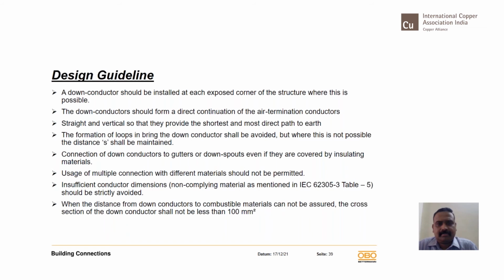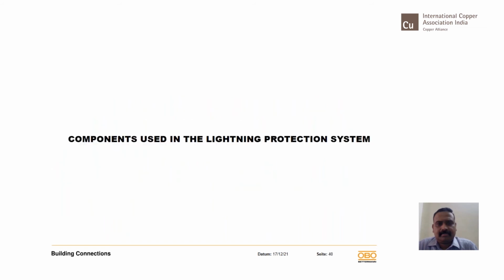Formation of S shapes or loops, like where you have a canopy and take the conductor from the top, go this way and bring it down, should be avoided. Usage of multiple connections should be avoided, and it should not be connected with multiple materials. For example, if you have an aluminum frame and a copper conductor, connect them only if it is really necessary, and that too with the help of bimetallic connections, and not directly without any bimetallic connection.